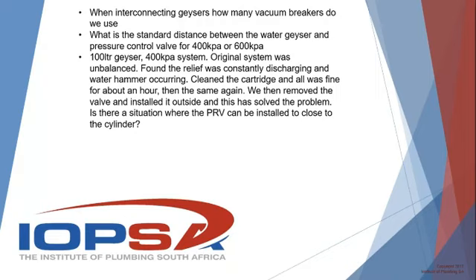From my side, yeah, he mentions the original system was unbalanced. So obviously when he moved the valve outside, then they balanced the system, and then it would take the water hammer and so forth away and the excessive discharge. But yes, as you say, you cannot have it too close to the geyser.